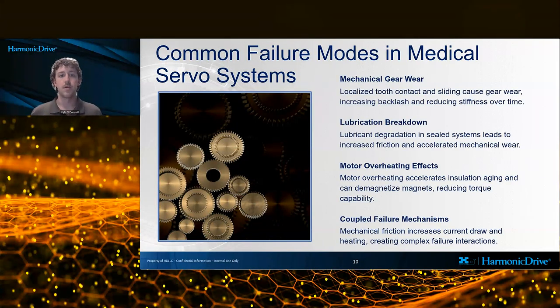So we're going to start by discussing how failure modes inform design decisions for highly reliable medical servo systems. On the mechanical side, gear wear and fatigue are dominant concerns. In conventional gears, localized tooth contact and sliding motion can lead to progressive wear, which is going to increase the backlash and reduce the stiffness of your system over time.